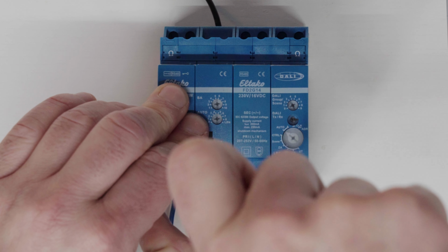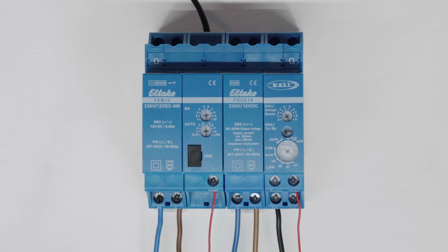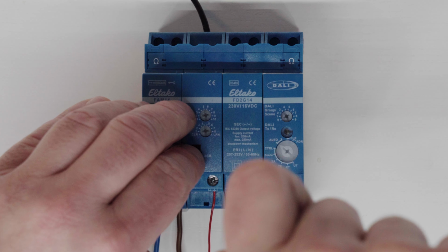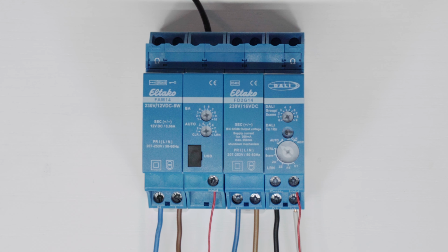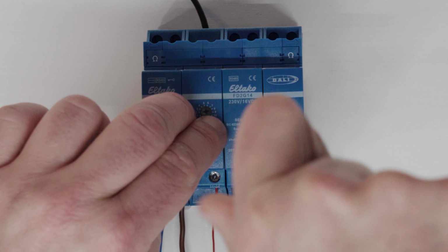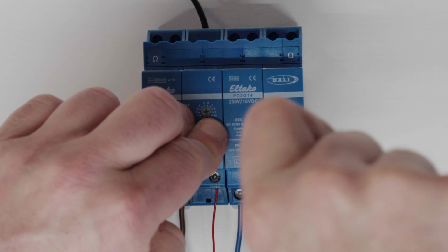The voltage for DALI devices is provided at the terminals DA plus and minus. DALI-2 event messages can be interpreted and output to the bus using the hold terminal. This allows an output via the telegram duplicator FD2G14 into the EnOcean wireless network. The maximum current for the DALI bus is 200 mA.